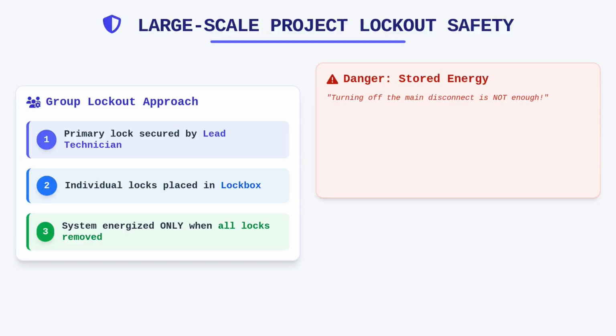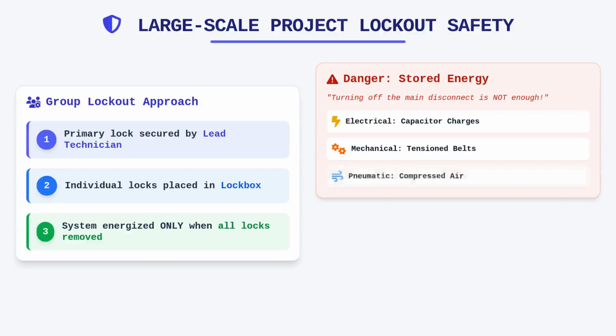Remember that simply turning off the main disconnect is often insufficient because systems frequently contain stored energy that remains dangerous even after the main power is cut. You must address residual electrical charges that might be present in capacitors, as well as potential mechanical energy stored in tension fan belts or trapped compressed air within pneumatic actuators.